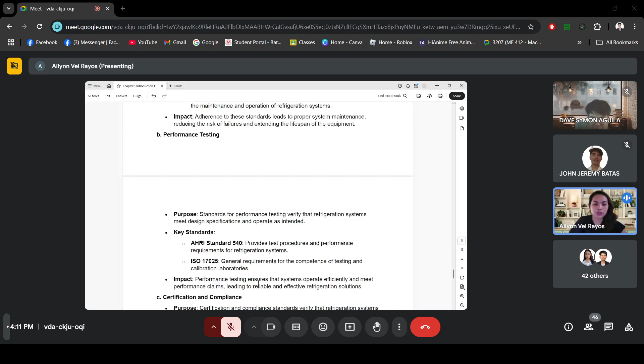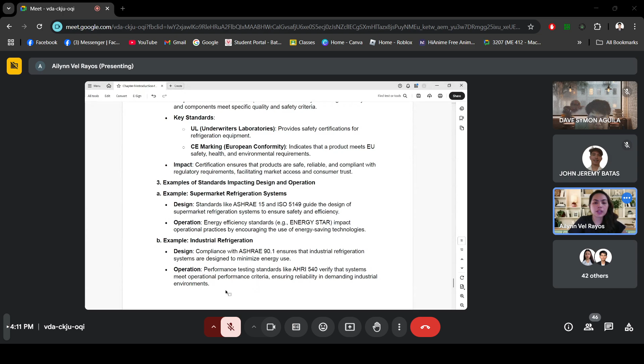So next, we have examples of standards impacting design and operation in actual applications. For example, in supermarket refrigeration systems, we follow ASHRAE 15 and ISO 5149, which guide the design of supermarket refrigeration systems to ensure safety and efficiency. In terms of operation, we have energy efficiency standards that impact operational practices by encouraging the use of energy-saving technologies.